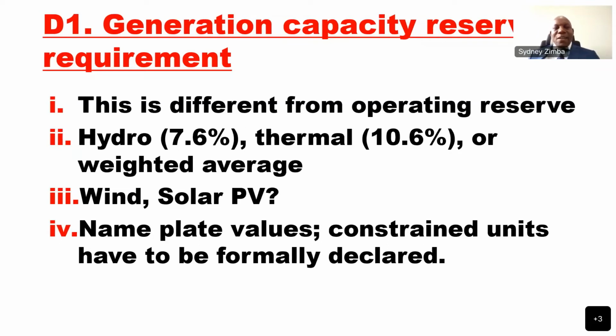So our guideline in SAPP is that if you're having hydro, at any given point in time you should have a reserve of 7.6%. If you've got 100 megawatts generation capacity or demand, you should have 107.6 megawatts of generation capacity. If you've got a combination of hydro and thermal, you calculate a weighted average.